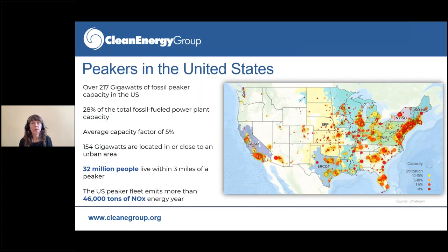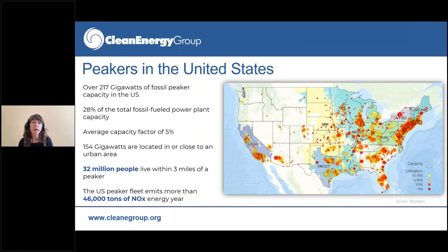This is a map of peakers in the United States — you can see how they're spread across the country and near population centers. There are over 217 gigawatts of fossil peaker capacity in the U.S. — 28% of total fossil power plant capacity, or almost a third, are peaker plants. That is why they are so important. Their average capacity factor is really around 5%, so this is a lot of plant and emissions that don't run all that often, which is why they are ripe for replacement. On this map, the size of the dot indicates the plant size in megawatts, and the color indicates how little it runs — the more red, the less it runs.